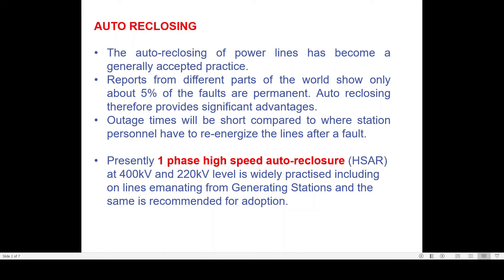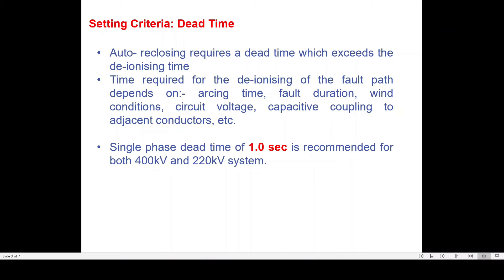This is the autoreclosing cycle we will discuss further. First, let us understand the different terminologies. The first is dead time. Dead time is required because whenever there is a fault and your distance protection relay has issued a trip command to the circuit breaker poles, the moving contact separates from the fixed contact and an arc develops. You have to quench that arc, and only when this arc is quenched and sufficient dielectric strength has built up between the contacts can you close the circuit breaker. This time required for build-up of dielectric strength and deionization of the arc is called dead time.